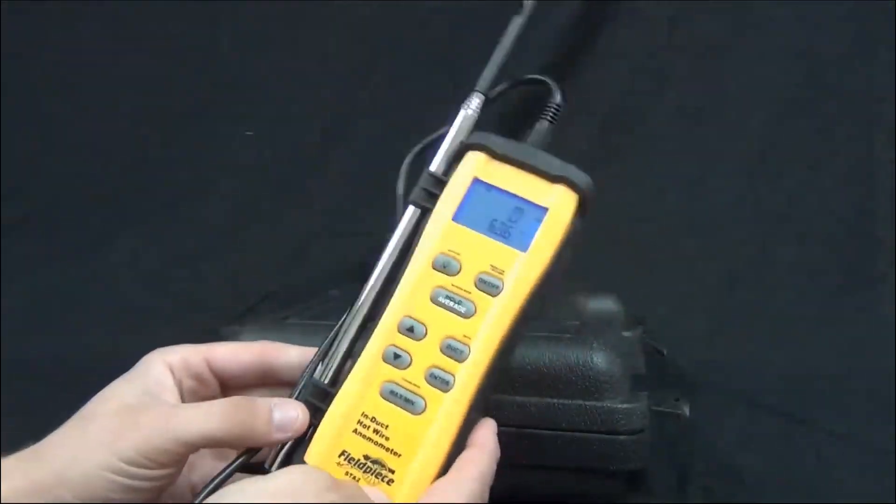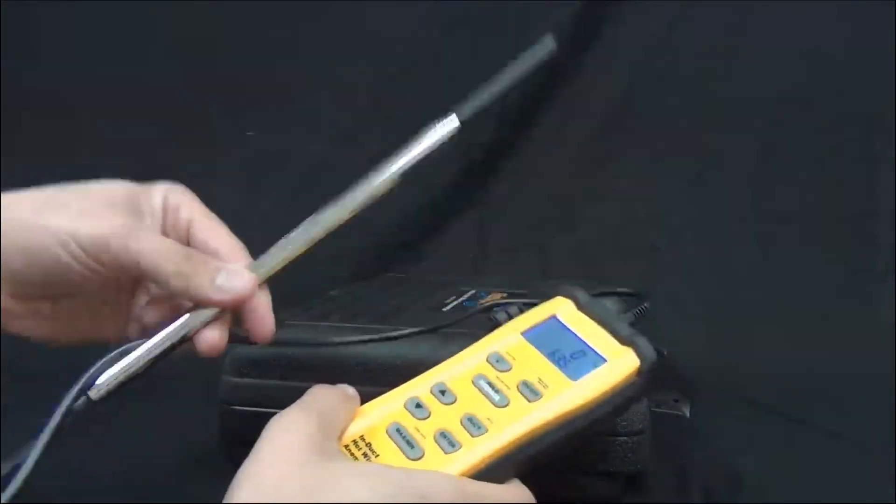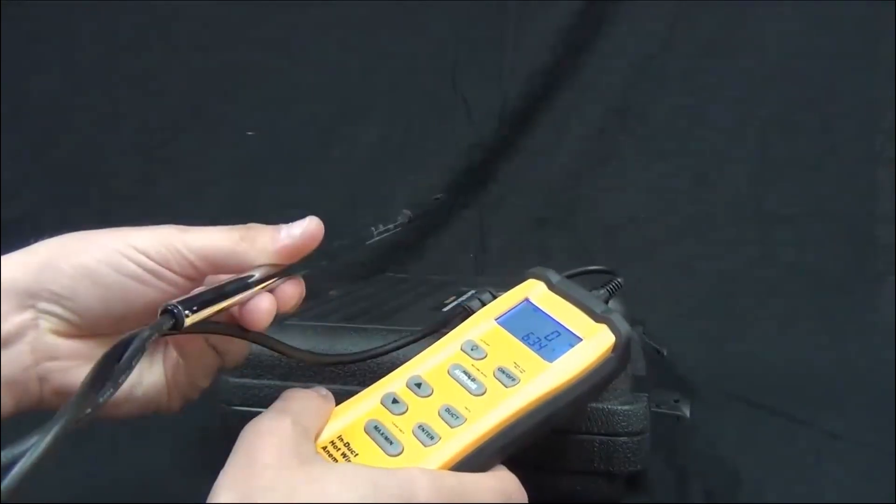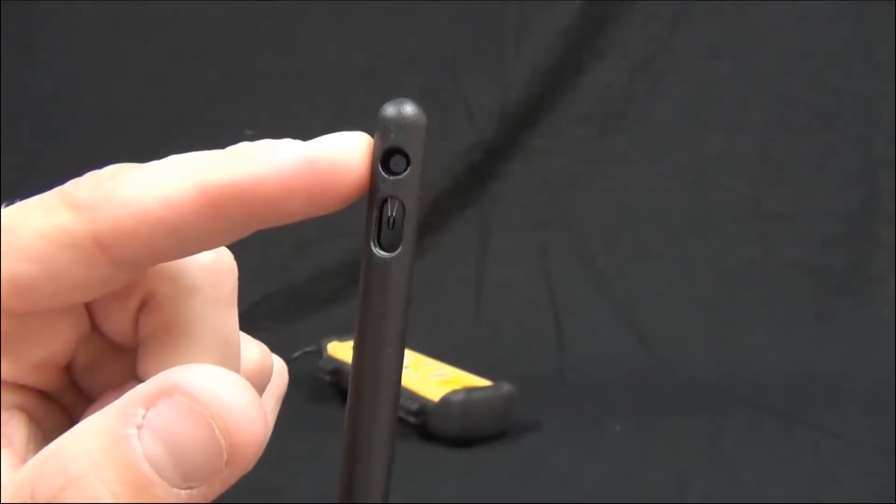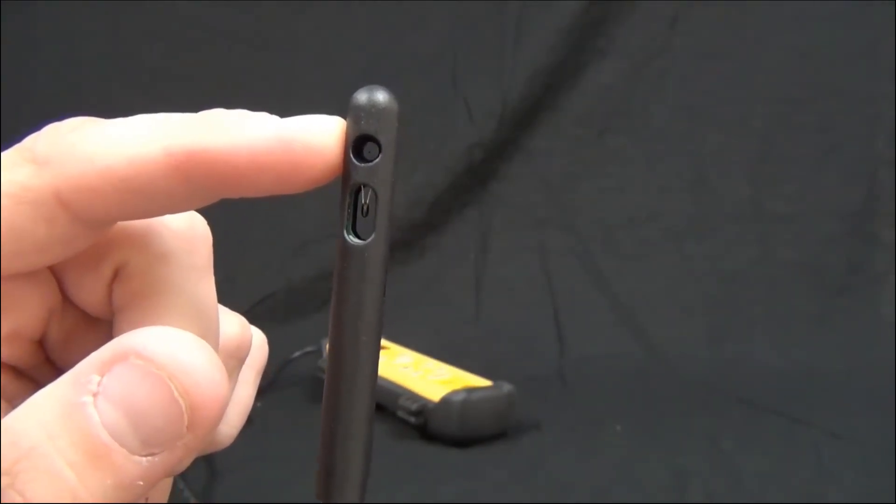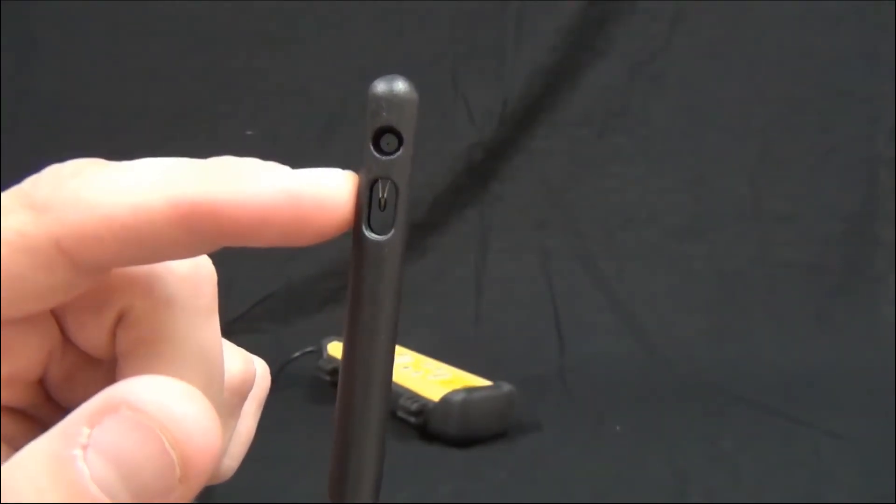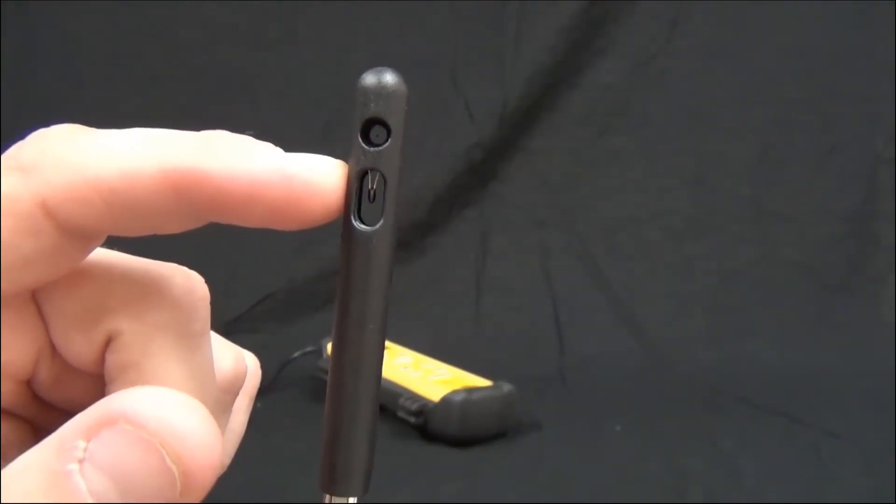On the STA-2 you can see that it has the wand. So let's check out the wand. Now what the wand allows you to do is to get air velocity in the duct. It has two sensors. The first, the top one, is the hot wire. This actually is measuring air velocity. And then we have a thermistor to measure temperature.